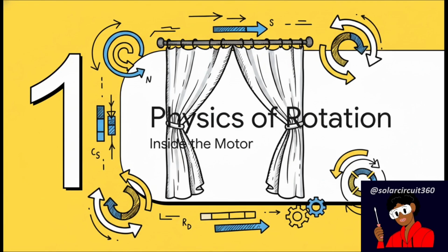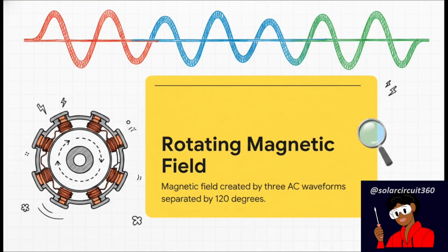Section 1. The physics of phase rotation. Let's pull back the curtain and see what's actually happening inside. To figure out why a motor spins backward, we kind of have to look at why it spins in the first place. Now, unlike a typical single-phase motor you'd find in, say, a household appliance, which usually needs start capacitors or special windings just to get going, a three-phase motor naturally creates its own rotation.